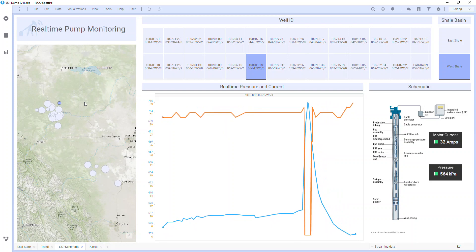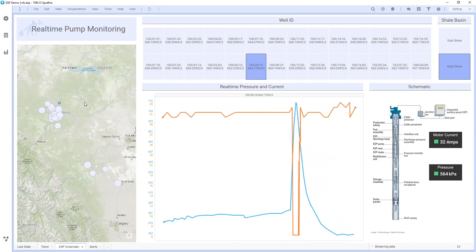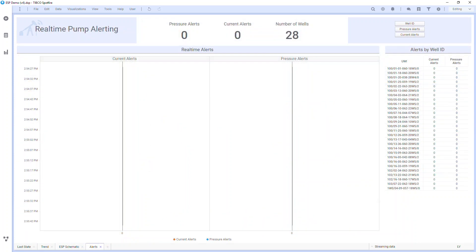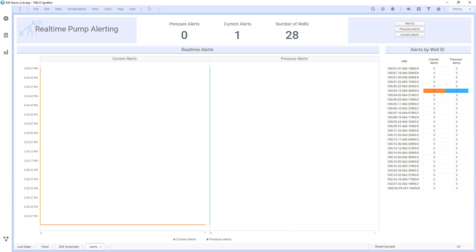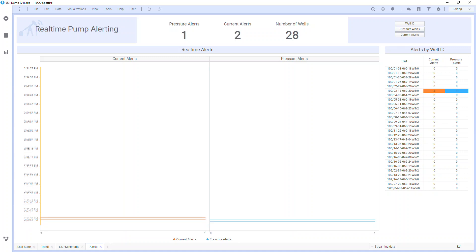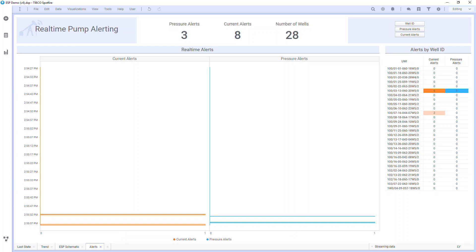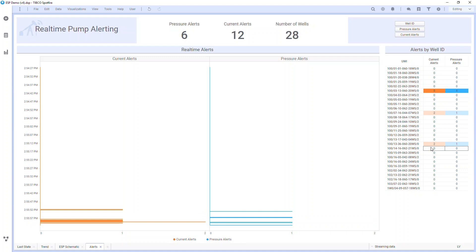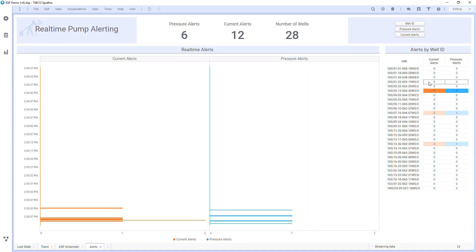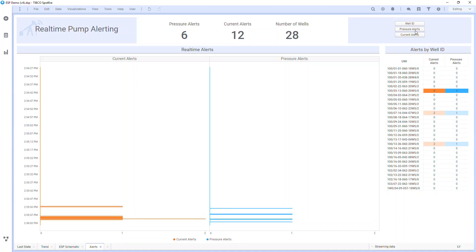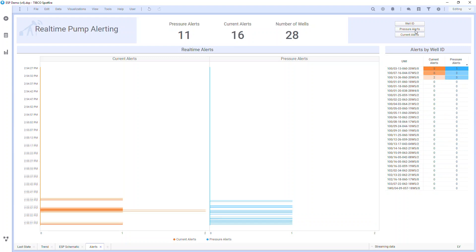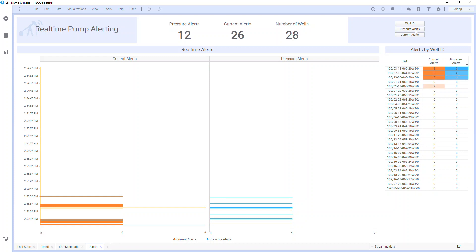As for those alerting thresholds I set earlier from the pressure slope — since I have the rules integrated in my TIBCO Streaming workflow, I have these alerts sent to Spotfire as well, which I can visualize in real time. On this page, you'll see a live bar chart scrolling up showing the number of alerts triggered over time. For this simulation, I also set up alerts for motor current, which are shown on the left. In the table at the right, I can see the number of alerts per well ID, which gives me a quick way of viewing the wells with the most alerts and most likely to encounter failure. I can easily hit this button in Spotfire to sort the table by current or pressure, allowing me to easily prioritize action for specific wells.